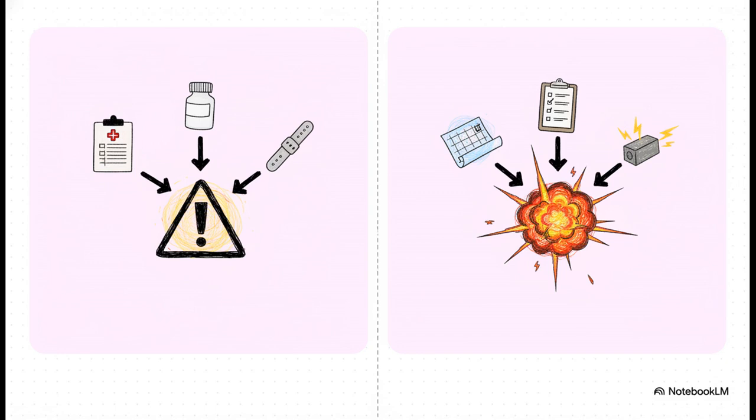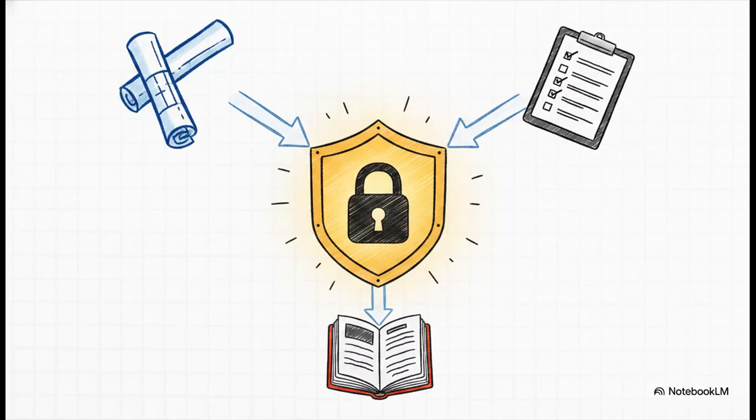If the drawing dictates a Zone 1 requirement, but an outdated Ex register allowed the installation of lower-rated Zone 2 hardware, well, you've now got an active ignition source sitting right in a highly explosive gas cloud. And that brings us to the absolute golden rule of hazardous area classification paperwork. 3 documents, 1 story, always. Rigorous document control is not just annoying administrative red tape. Keeping a single master revision log and ensuring these 3 deliverables are cross-referenced and synchronized is quite literally a life-saving safety control.